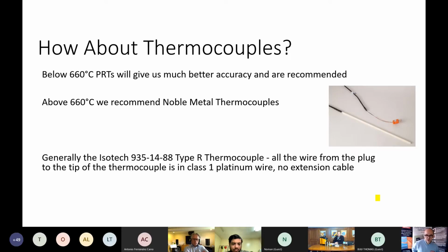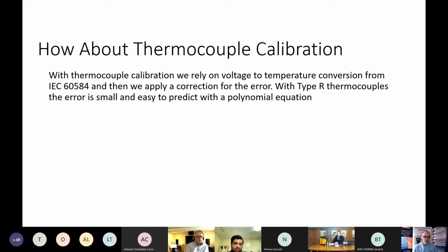So a noble metal thermocouple is a good choice, and we would recommend in general the Isotech 9351488. This is a type R thermocouple, but the wire all the way from the plug to the tip of the thermocouple is platinum wire, the best wire commercially available, no extension cable. And so that's best practice. So that's where we'd recommend people. So with thermocouple calibration, we rely on the voltage to temperature conversion from IEC 60584, which is the standard, and then we apply a correction for the error. Now with a type R thermocouple, that error is small and it's easy to predict with a polynomial equation. So this is what we do.